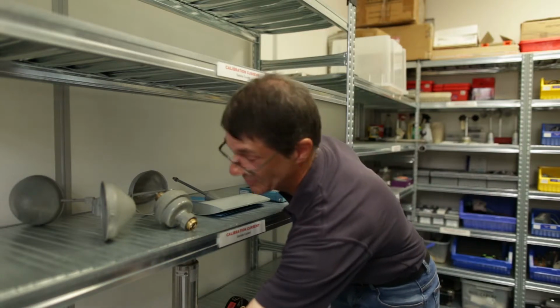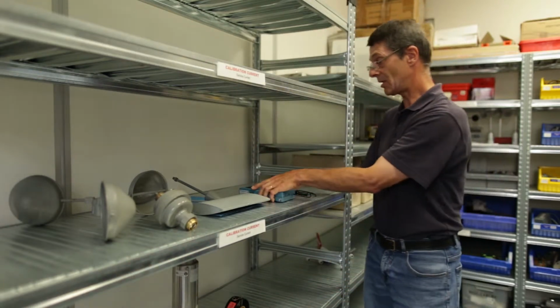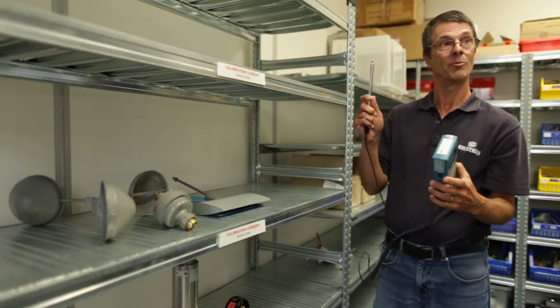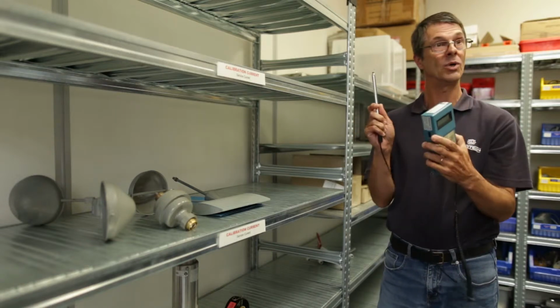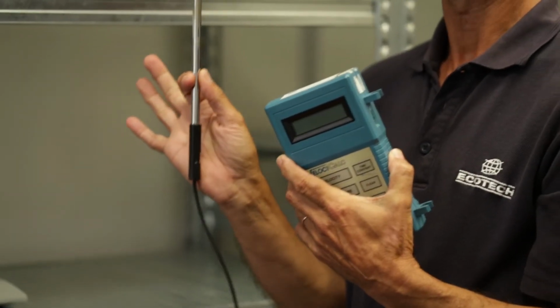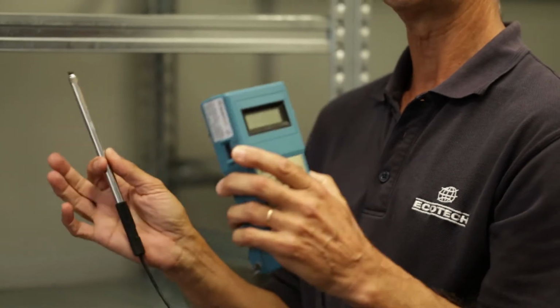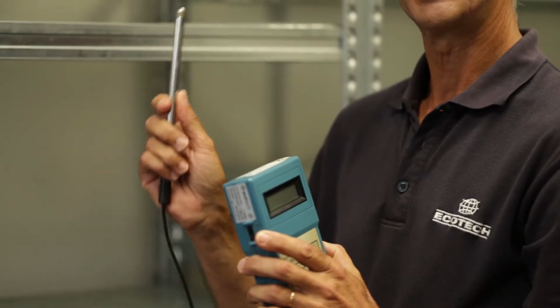We have another type here which is a thermal anemometer, which uses a very thin heated wire and uses the cooling effect of wind to measure wind speed. This is good for very low speed applications.